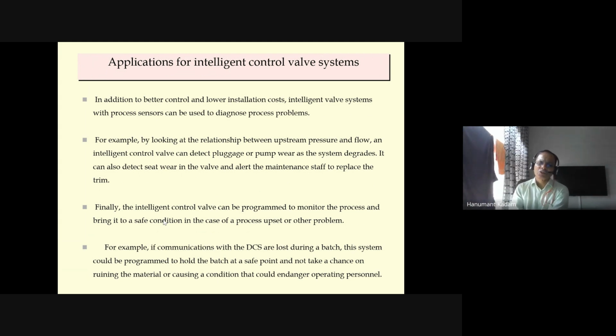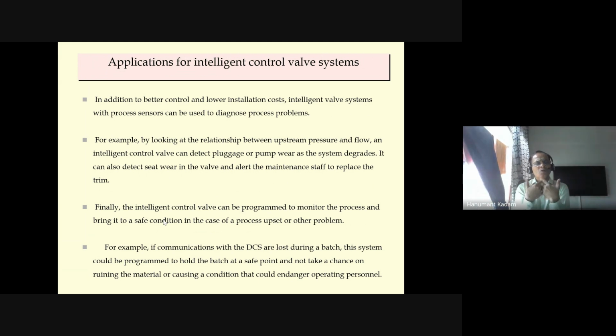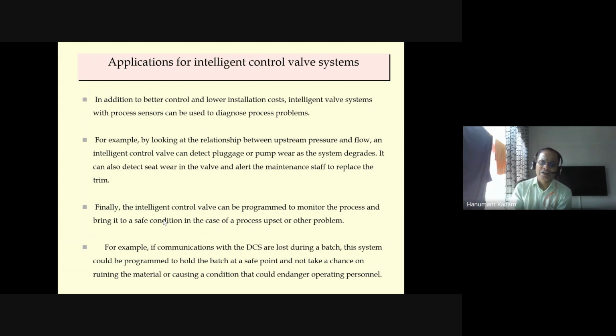For example, if communication with the DCS is lost, which is one problem mentioned, it can happen for many reasons. With communication lost during a batch, this system could be programmed to hold the batch at a safe point and not take a chance of ruining material or causing a condition that could endanger the operating personnel. It means to avoid this, the batch has to be stopped instead of going to the waste reaction. If something happens further, that product either has to be damaged, or you cannot recycle it, or that can cause operational hazards.